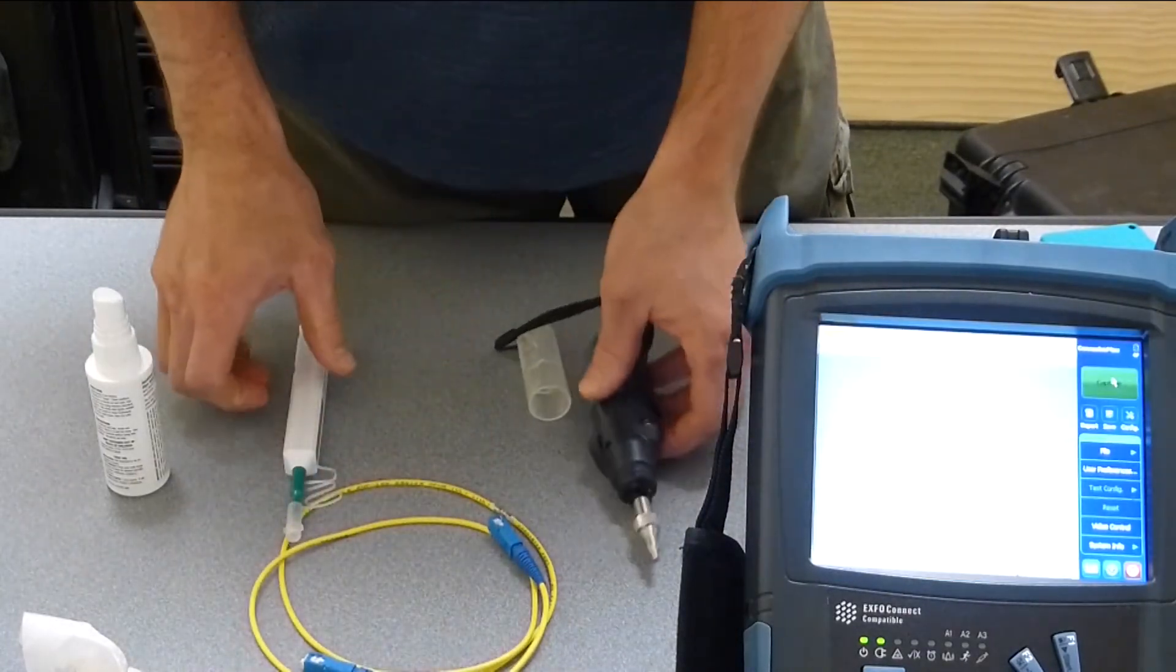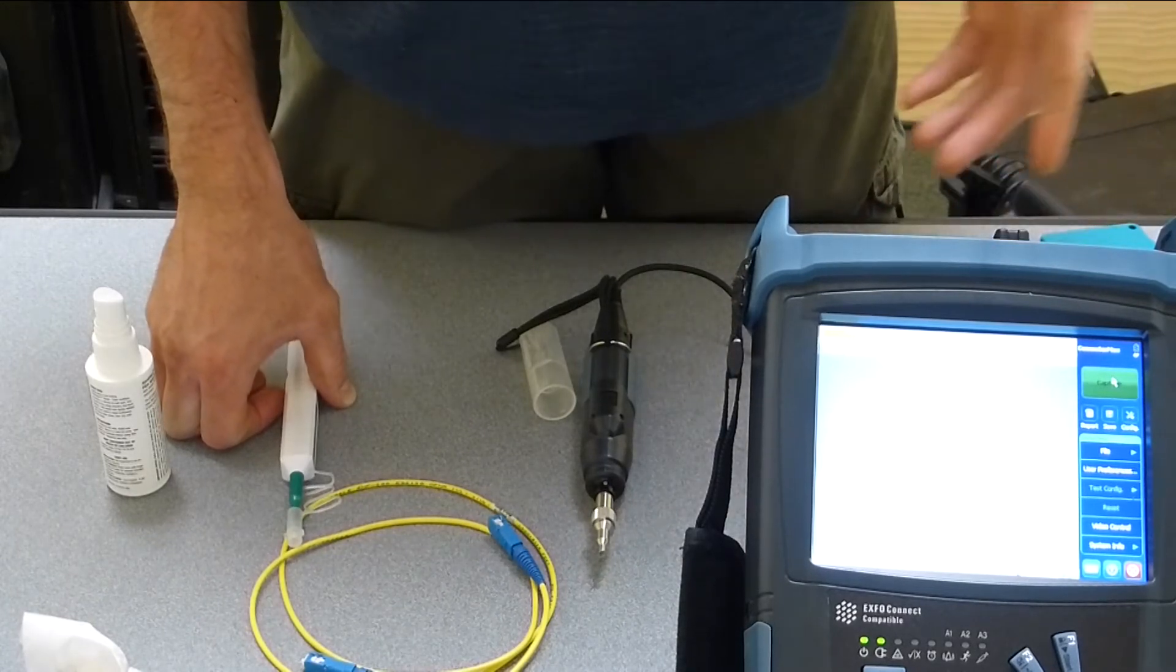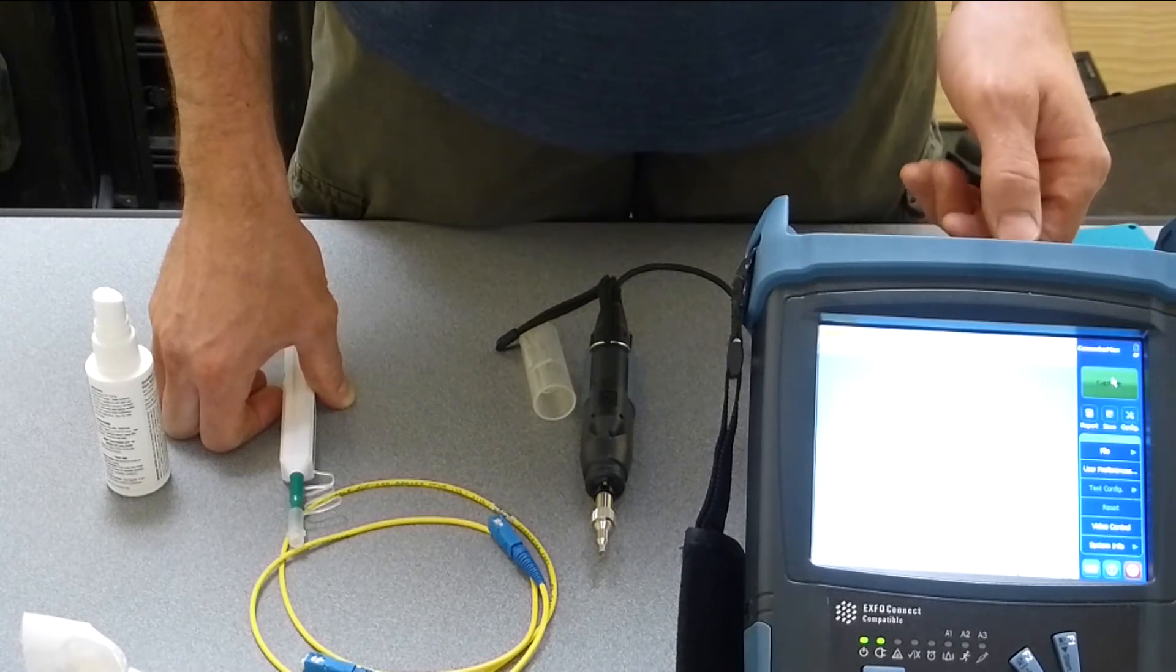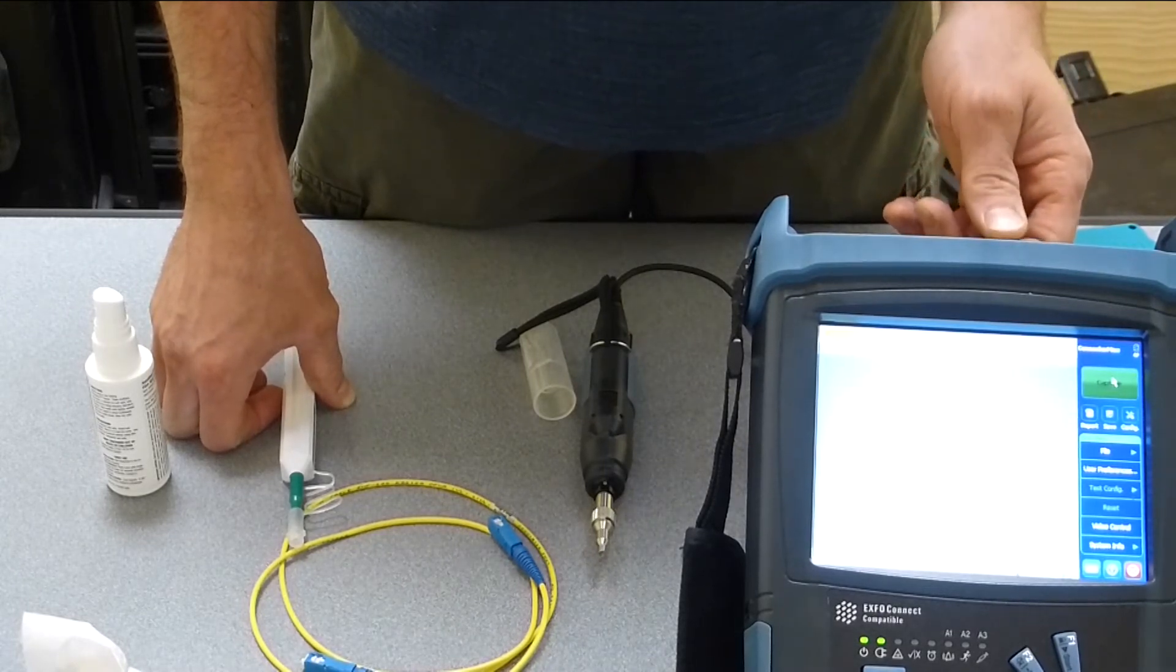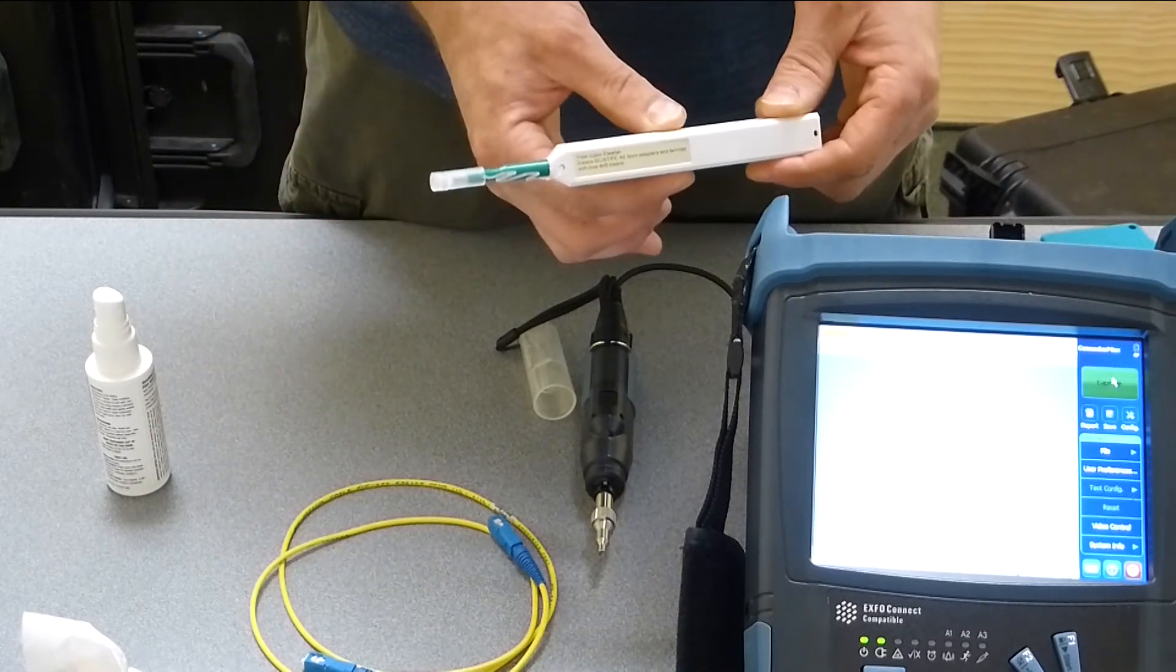Another place that people really forget to clean is their OTDR port. And the OTDR port is really important that it stays clean because with a damaged connector or bad transmission, we're going to get inaccurate test results. So today we'll talk about using the one click cleaners.